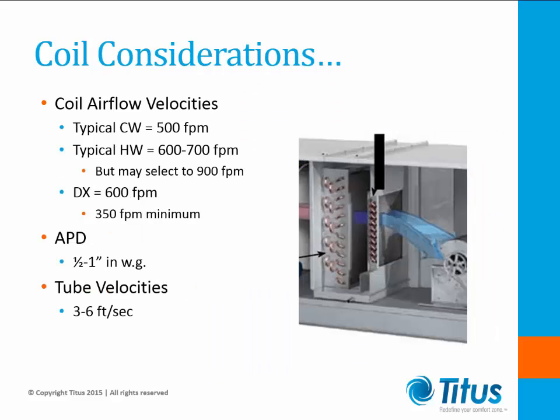Many times we look at the coil velocities as ever-present items that we need to control within the air handling units. Cooling coils with air velocities above 500 feet per minute is the point where water droplets can leave the outer edge of the fin. This is called moisture carryover. Air handling units should be designed to avoid velocities greater than 500 feet per minute on cooling coil configurations. Heating coils, on the other hand, can run higher velocities since moisture carryover is not present. Many times the heating coils can reach up to 900 feet per minute.